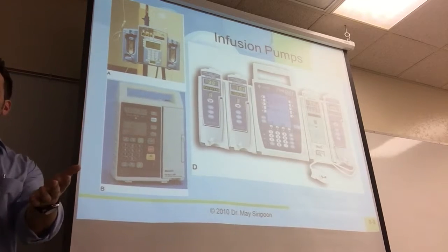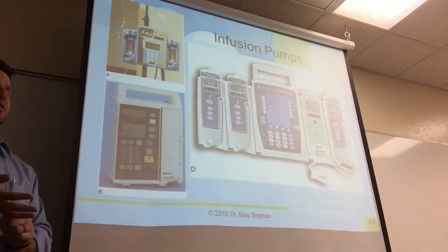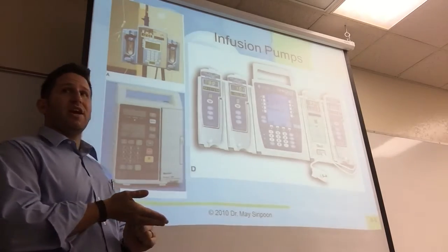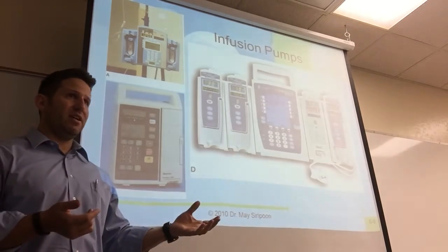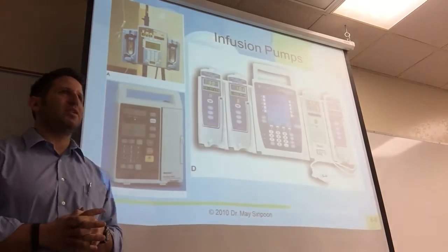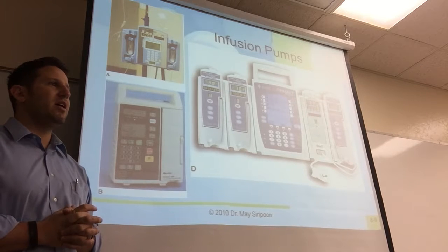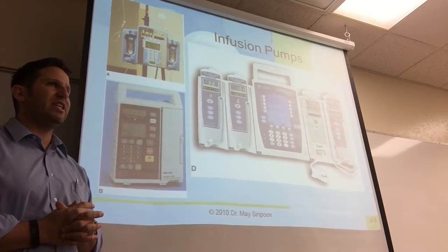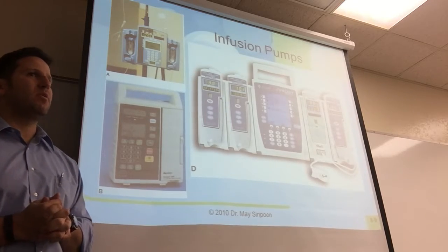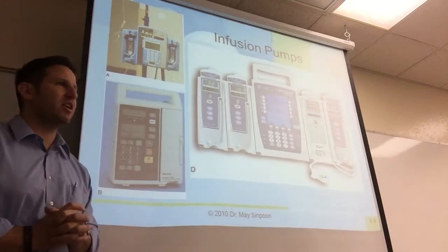Human error. It requires a human to put it in. So if I put the wrong, excuse me, not the wrong rate, but I put the wrong patient weight in there, then all my calculations are off, right? So what if it was a pediatric patient that weighs 7 kilos and they're in septic shock and they need to be on dopamine, and I put them at 70 kilos? Will that change my rate significantly? Yeah, times 10, right? Which could be a bad day for that baby. So there's still some human error that could happen.